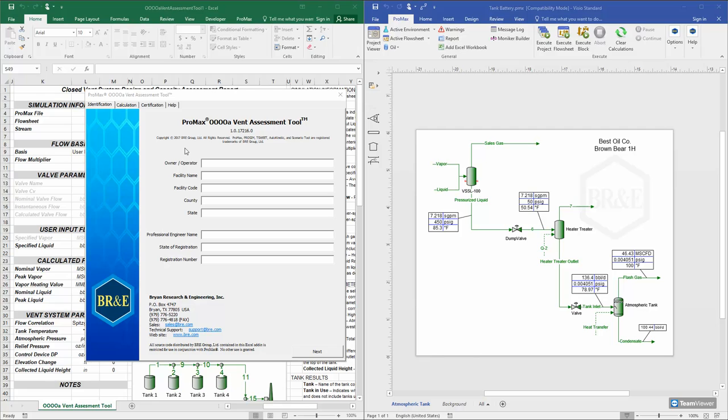In order to determine whether vent systems from atmospheric tanks are of adequate design, we must first determine the peak flow through our facility. We generally talk about flow through a facility in average daily production, what we will call nominal flow. However, the actual flow through the facility is typically not constant, with level control valves opening and closing at different intervals. When we speak of peak flow, we are talking about the maximum flow rate the vent system may experience during normal operation. Generally, this value is going to be greater than the vapors produced from nominal flow.